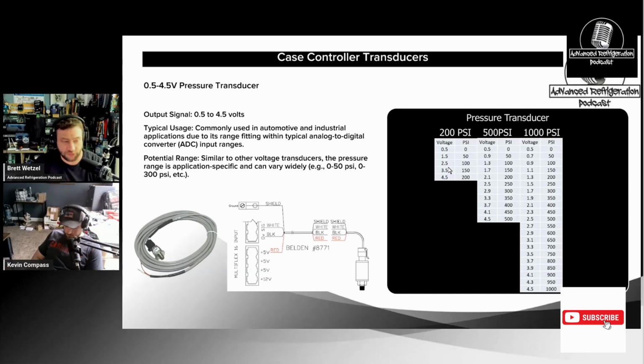Like I said, sensors are not linear, pressure transducers definitely are. So that's what I did here. I basically made my own Interpolation Master in an Excel spreadsheet. So you can see here, I put 0 to 200, 0 to 500, and 0 to 1,000. So obviously 2.5 is just about right in the middle. So that's going to be 500 pounds in the middle for 0 to 1,000, and so on and so forth. But these other numbers, if you're getting an odd number and it's not making any sense, maybe someone has an offset in the controller or something along those lines. That is the next point I go to.